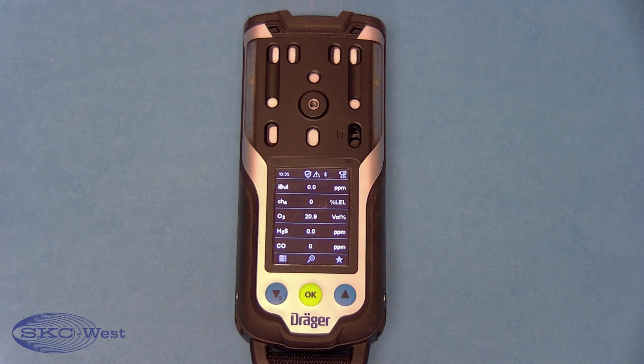There are 2 different peaks available on the X-am 8000 or 3500. The shift peak is the highest reading since the instrument was turned on. Every time the instrument is turned off, the shift peak is automatically cleared. The application peak is your traditional peak that will store until you clear it using the methods we are about to talk about.